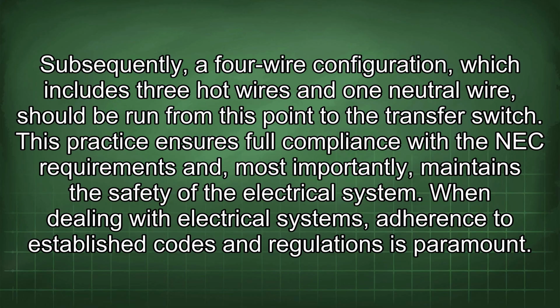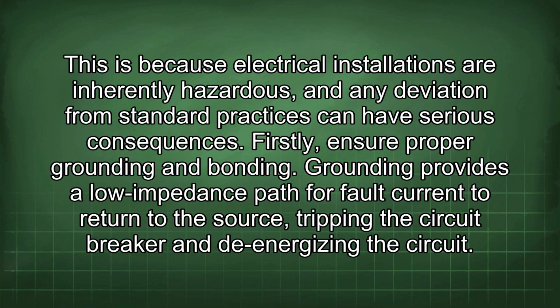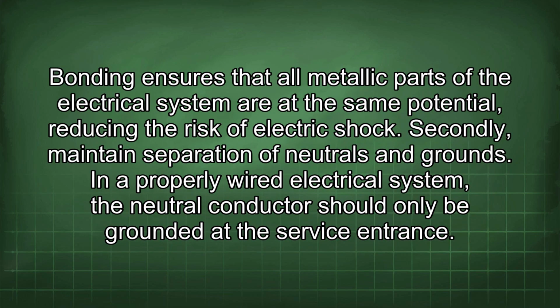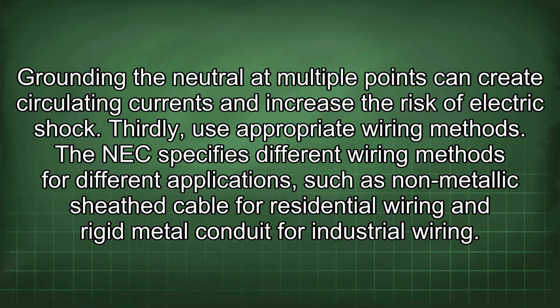electrical system. When dealing with electrical systems, adherence to established codes and regulations is paramount. This is because electrical installations are inherently hazardous, and any deviation from standard practices can have serious consequences. Firstly, ensure proper grounding and bonding. Grounding provides a low impedance path for fault current to return to the source, tripping the circuit breaker and de-energizing the circuit. Bonding ensures that all metallic parts of the electrical system are at the same potential, reducing the risk of electric shock. Secondly, maintain separation of neutrals and grounds. In a properly wired electrical system, the neutral conductor should only be grounded at the service entrance. Grounding the neutral at multiple points can create circulating currents and increase the risk of electric shock.